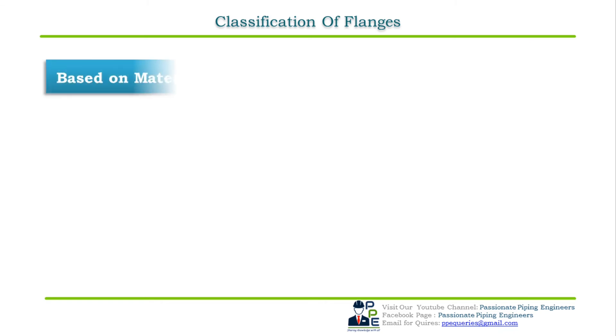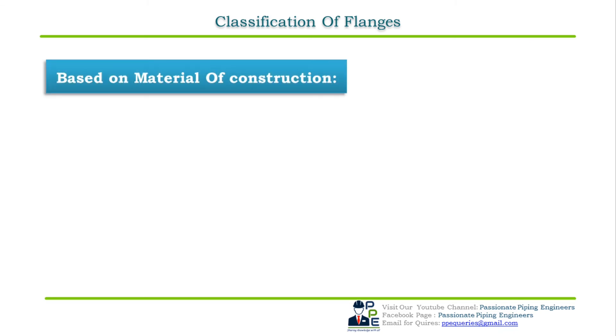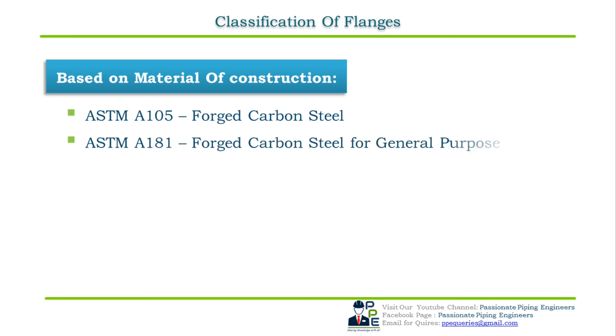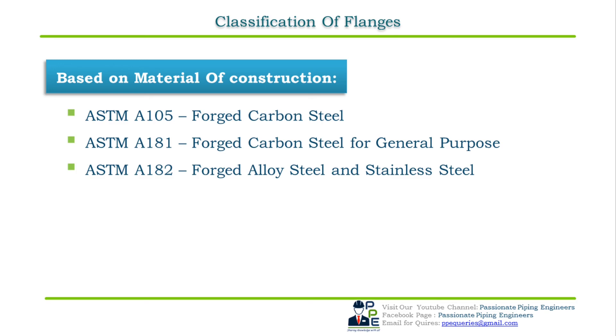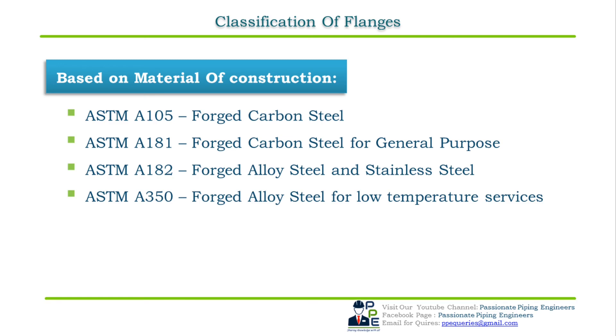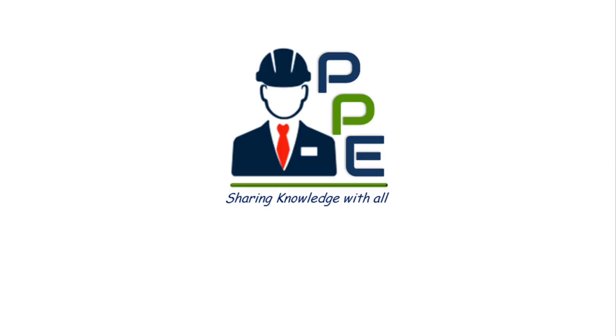Based on material of construction: flanges are normally forged, except in very few cases where they are fabricated from plates, in which case they should possess weldable quality. Common materials of construction are: ASTM A105 for forged carbon steel, ASTM A181 for forged carbon steel for general purpose, ASTM A182 for forged alloy steel and stainless steel, and ASTM A350 for forged alloy steel for low temperature services.